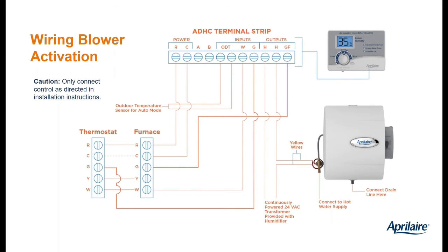Let's go through the wiring. The key here is I want you to understand that this wiring is very straightforward. There's not a lot going on here at all. So what we've got in this picture is, starting at the left, you've got your thermostat, you've got your furnace. So those are already going to be wired up, of course. R to R, G to G, Y to Y, W to W. Maybe you've got a C terminal on your thermostat, maybe not. That's why it's dashed. Anyway, so that's already existing.